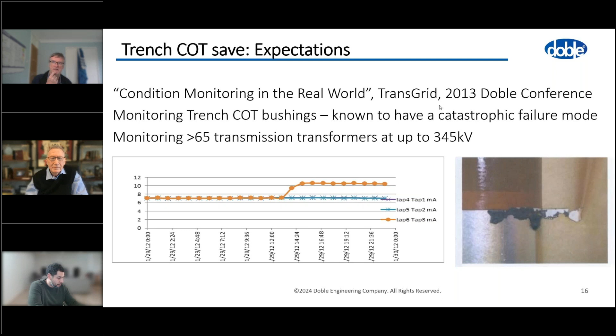And what we're looking at here is partial discharge over several days to weeks inside the main tank of the transformer. We do a statistical analysis of a spectrum to say, yes, there is partial discharge. We give an indication of how strong it is. This is not a phase resolved plot. And you can see this partial discharge rises and falls, rises and falls. And it was somewhat disturbing. It wasn't to the point where we were going to panic. The interesting thing was similar transformers on the same site had shown similar types of effect as a result of partial discharge from loose insulators on the isophase bus in the generator station. And it was intermittent, the same way this is intermittent, but this is right in the main tank.